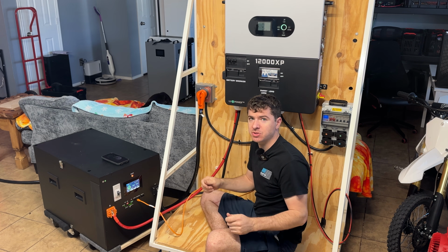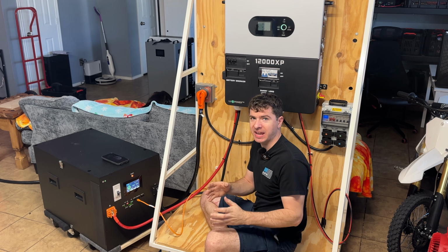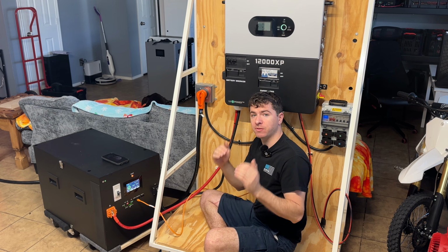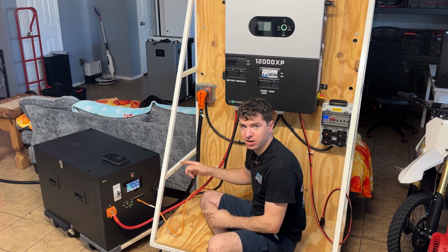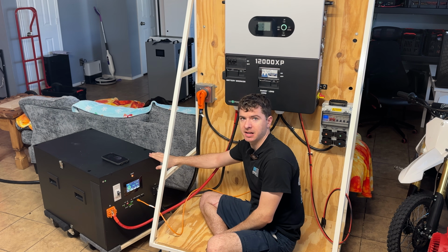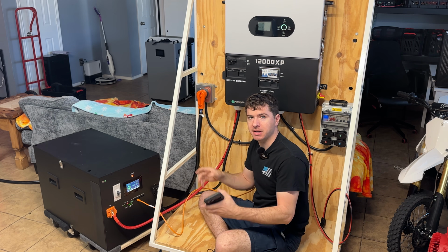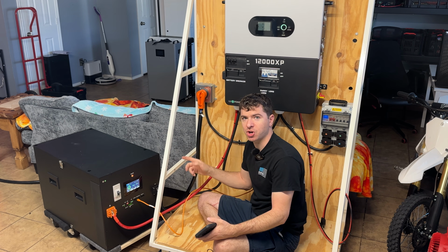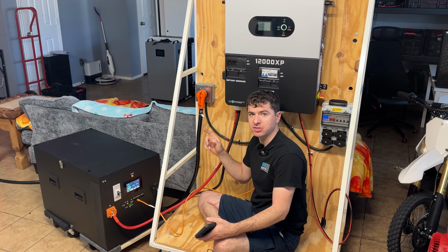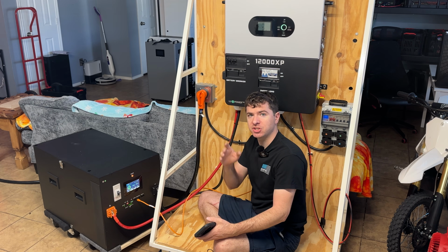The charge cable I'm using is going to give me a max power of about 40 amps at 240 volts, which is very close to 10,000 watts. And that's going to pull 200 amps on the DC side. Now in the JK BMS app out of the box, the battery's BMS max continuous charge current and discharge current was set to 200 amps. So I did go ahead and raise that to 250 amps.